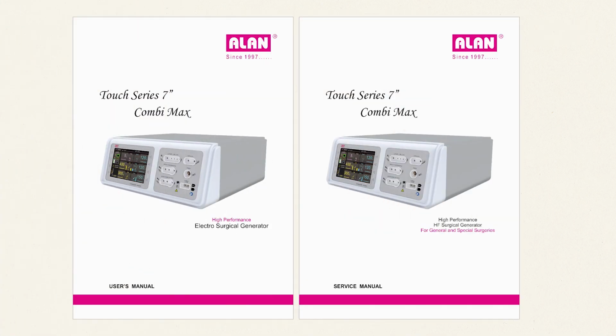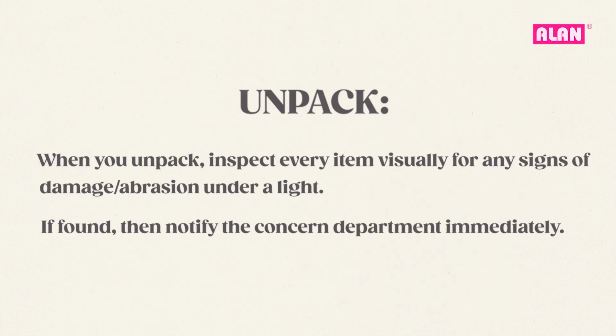User and service manual. It is intended as a guide for using Alan's equipment. Further, it has technical and product details, instruction on safety and effective use, basic troubleshooting steps, and maintenance guide. When you unpack, inspect every item visually for any signs of damage or abrasion under the light. If found, then notify the concerned department immediately.